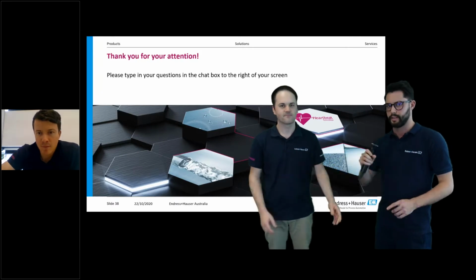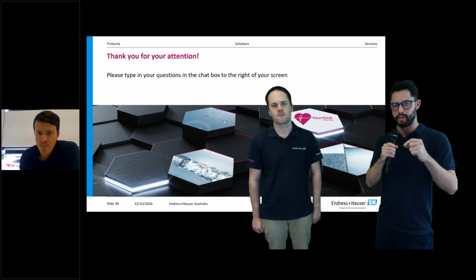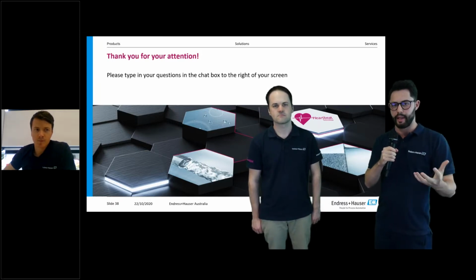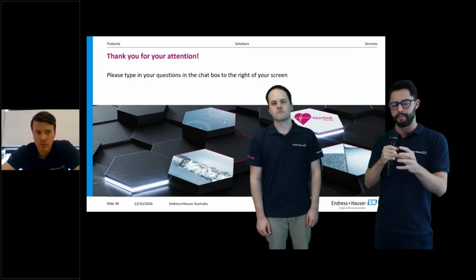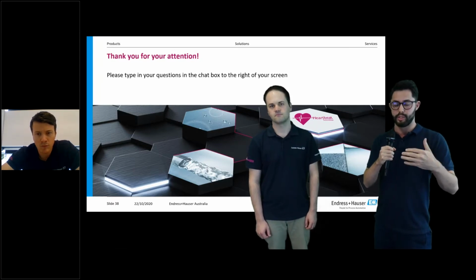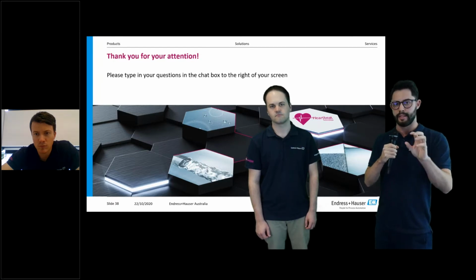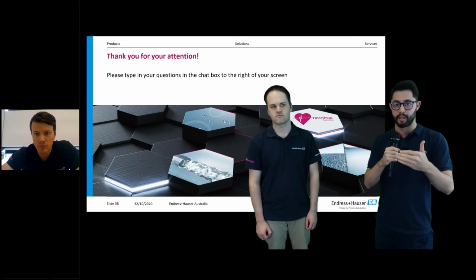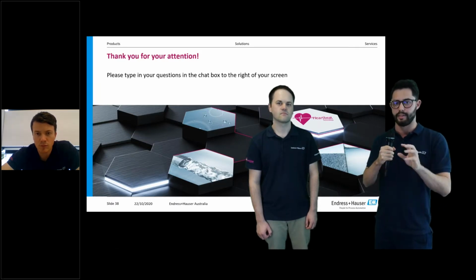Yes. Just a couple of comments. The verification does not have any metrological aspect. So when you run a verification, you're assessing and evaluating the health and the condition of your device. You're not comparing the measurement values to another standard. So you can use this as a tool to justify, for example, the extension between the calibrations, but you cannot use this as a tool to say, okay, my equipment is measuring well, because you're not comparing your device with the primary standard. So there's a slight difference.